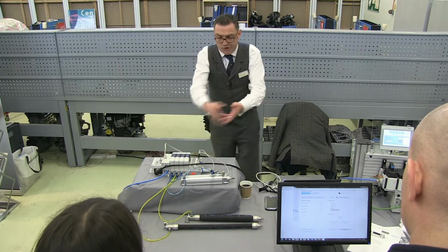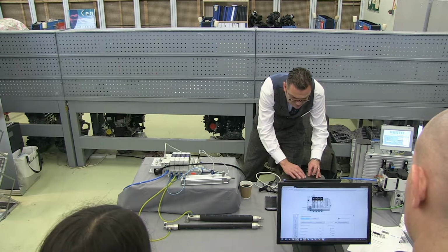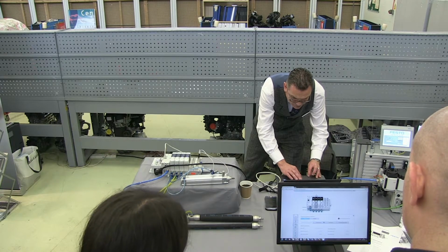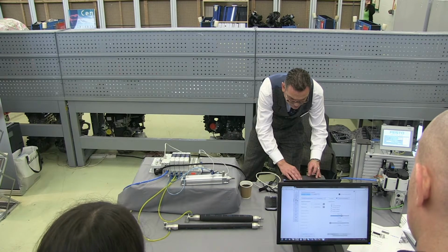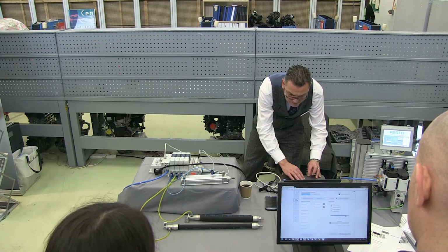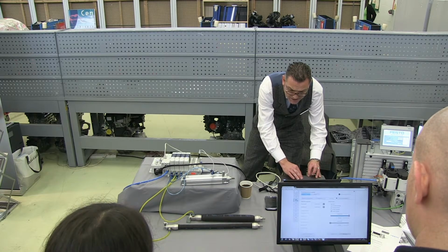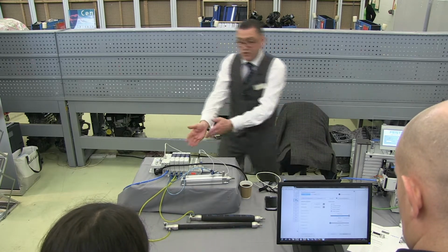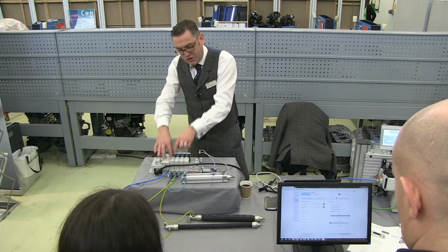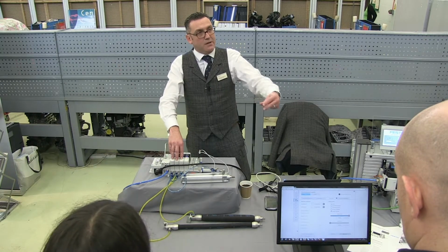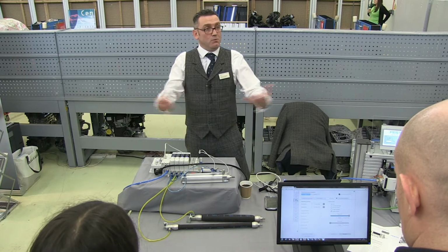We can also change the functions of the valves all over the place. So all 4 valves are identical. On the second one, what I've got is a proportional pressure control rather than a straight control, using exactly the same hardware that I've just used in more of a standard direct control mode. So you can see by changing the software functionality at different times of part of the machine cycle, you get a lot more flexibility within your machine control.